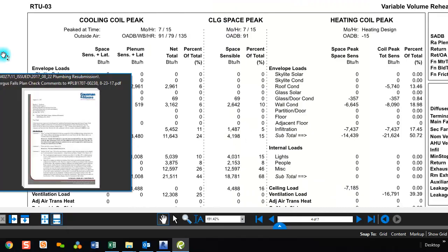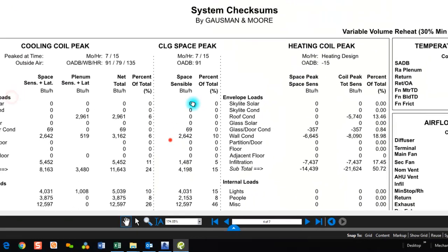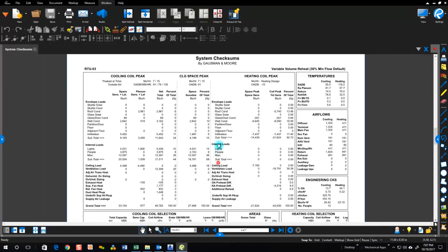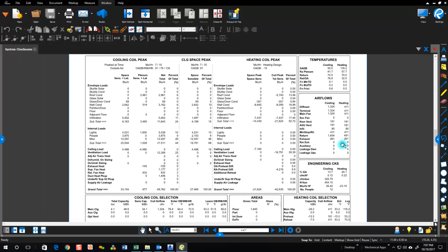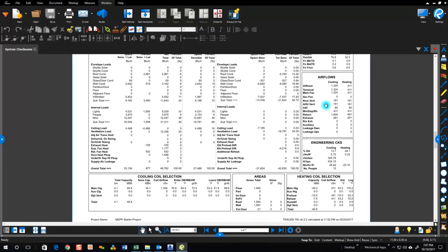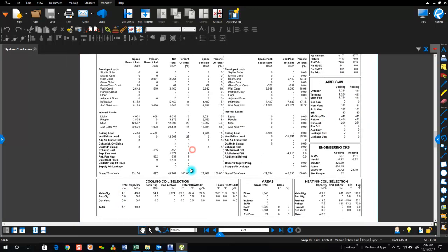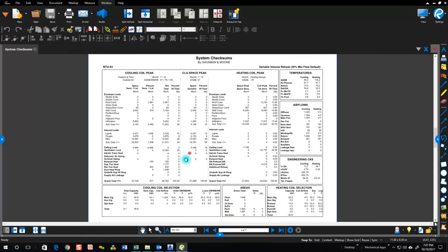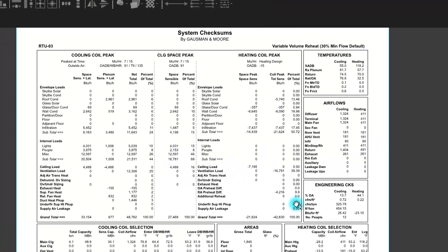I have some loads that were just completed for this sample project, and rooftop unit 3 is what we're going to be working on. It's about 1300-ish CFM, 4.1 ton load, so I'm going to end up placing a 5 ton unit and then we'll go from there. Our outside air is 181 CFM.